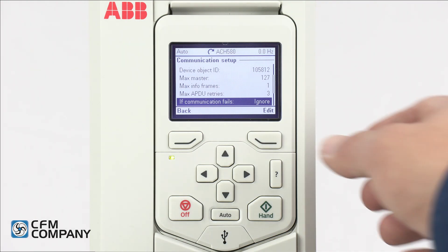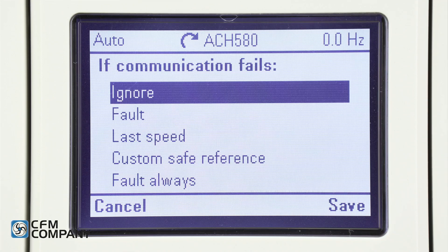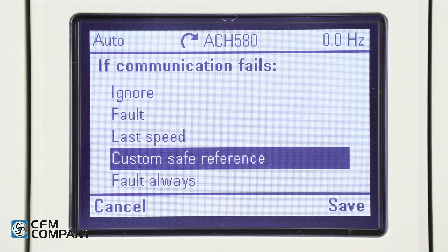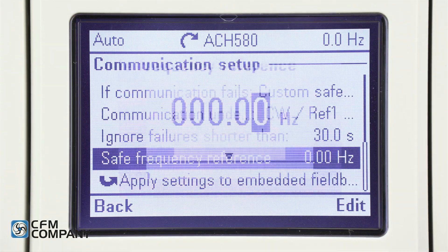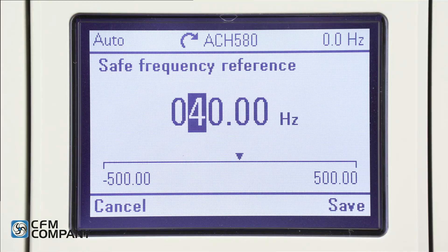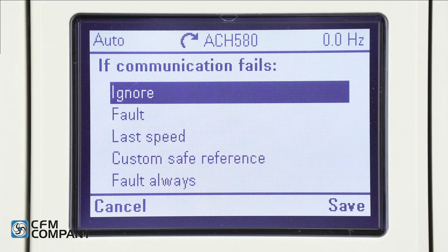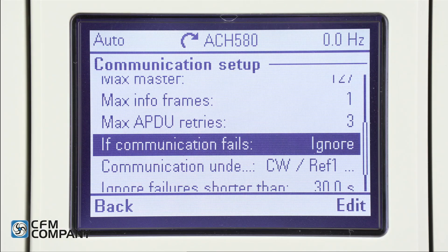With if communication fails highlighted, press edit. The correct choice depends on the critical nature of the equipment and the requirements of the owner. Remember that the loss of communication action can always be changed later as needed. If custom safe reference is selected, an additional menu item — safe frequency reference — is added; simply edit the desired safe frequency reference value and press save. For this example, keep the default value of ignore. Press save to return to the communication setup menu.